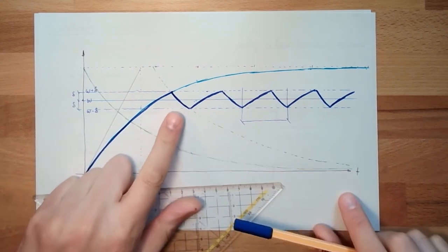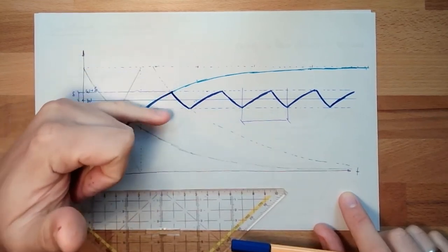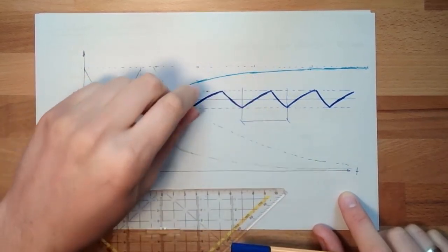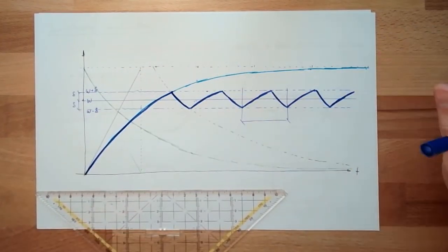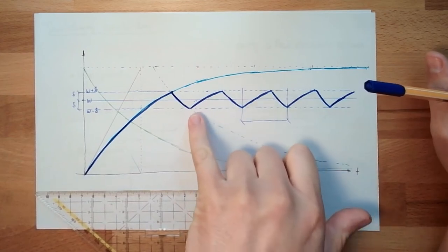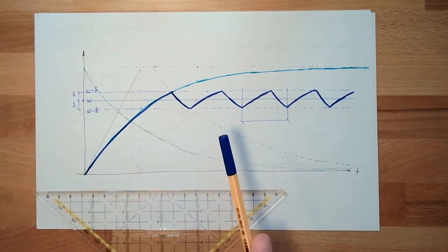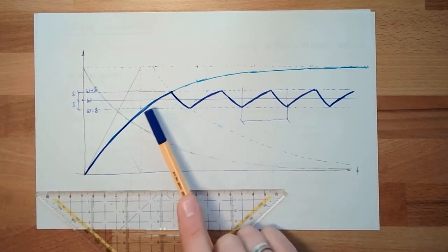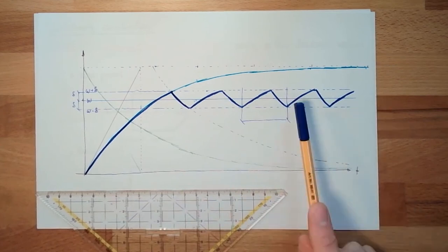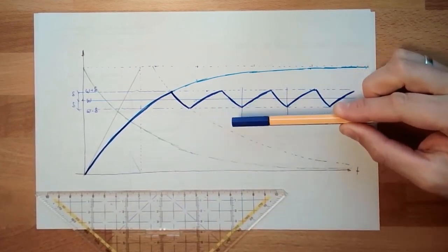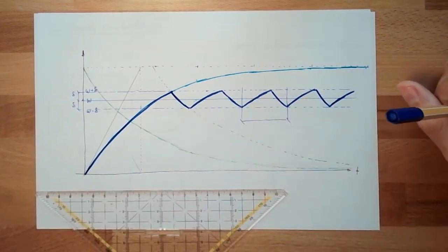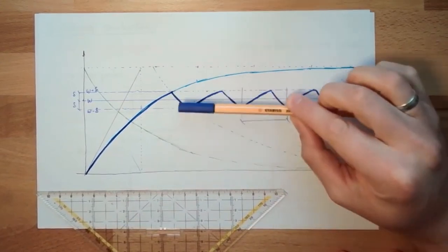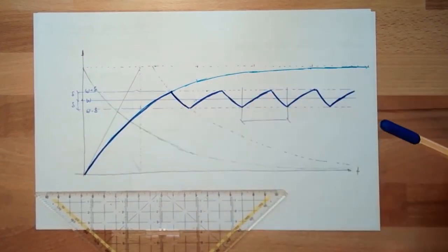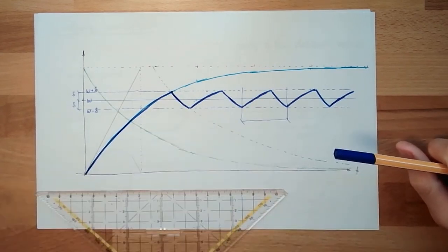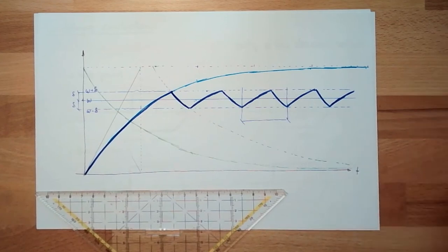Okay. And unluckily these fluctuations also change a little bit if you're up or down, because it takes really long to go up the same amount. It's shorter than to go down, but also it is depending where we are. This is a typical sign of switching controllers, this inhomogeneous behavior. There is always jittering around. Okay? There's always some period swinging around the wanted value, around the set point. This is why I said these things are used if it's not meant to be that accurate. Okay.